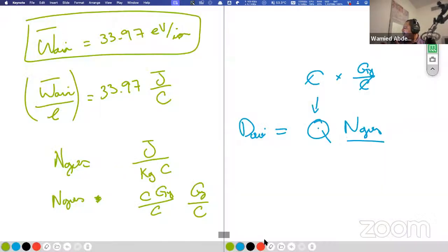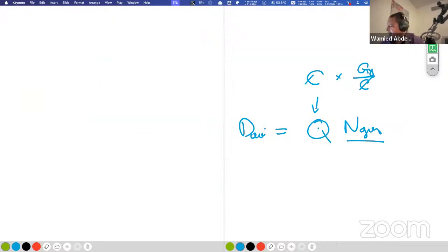So if we think of a charged particle, for example an electron or a proton, as it's going through air, it's going to ionize the medium. And we get positive and negative charges produced within this track of our charged particle that is crossing the chamber. So when charges produced from the same track recombine with one another, this is called initial recombination.